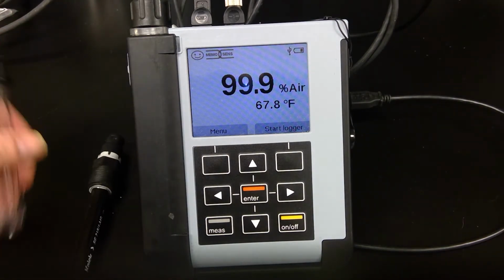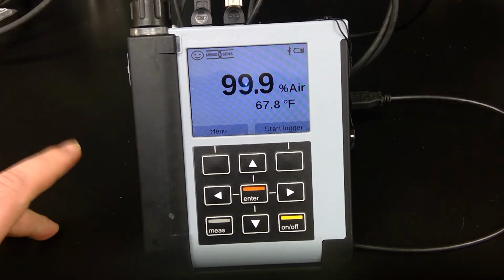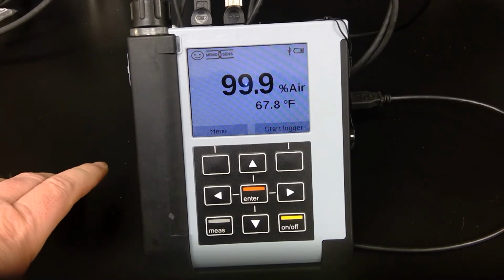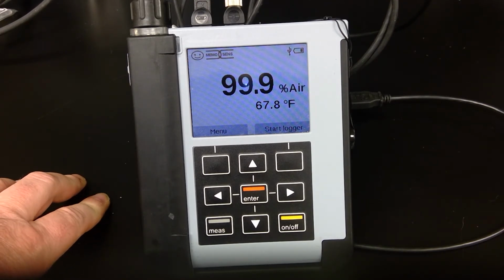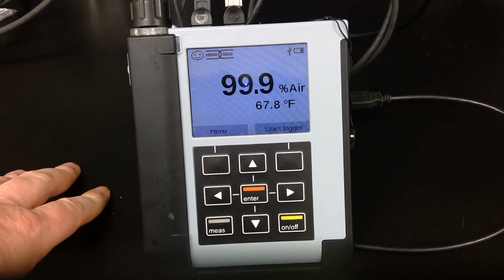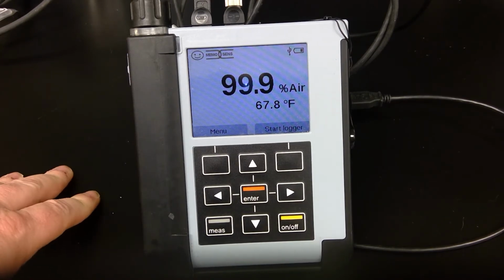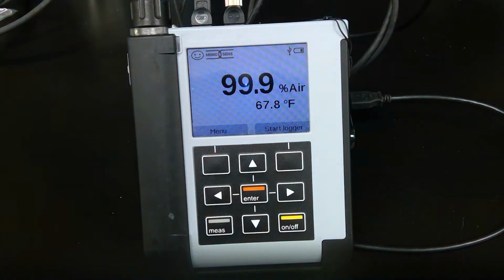What you do to prep this for calibration is, number one, make sure it's been polarizing for at least 6 hours. And again, as we said in previous videos, ideally you would do your PM at the end of the day, powered up overnight with a transmitter or the Portavo, and then the next morning the sensor will be fully polarized. Otherwise, if you try to calibrate it without polarization, meaning the sensor was either straight out of the box or you pulled it off an application and left it sit unpowered for a period of time, it's going to drift after calibration. So again, polarization is very important.